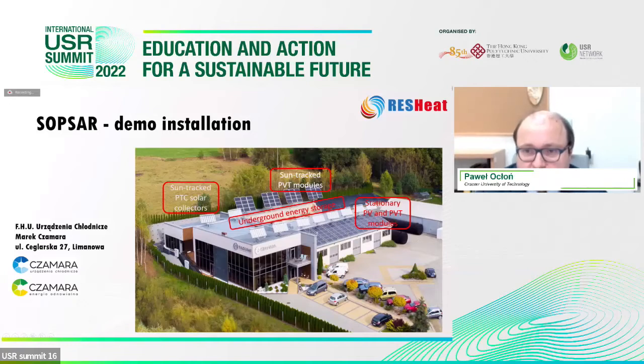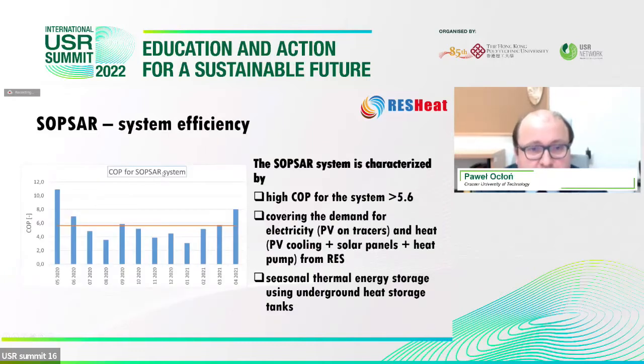We also have these underground storages, which we can see, for example, here. They are installed under the basement. And then this system was tested. What we can see from it is that we are able to achieve quite a good COP, coefficient of performance, of the system, over 5.6.